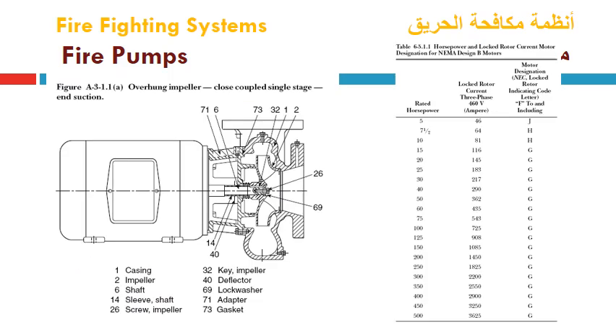Here this slide shows an overhung impeller for a close coupled single suction single stage end suction pump. This is the suction flange and the impeller is located here. All the numbers are shown below the figure, and the shaft is fastened with the key or bolted here to the impeller eye, and this is the volute casing, and this is the discharge flange. This is the close coupling, which is hidden here between the short pump casing and is close coupled to the electrical motor with its shaft going this way, and this is the center line of both the electrical motor and the end suction pump.